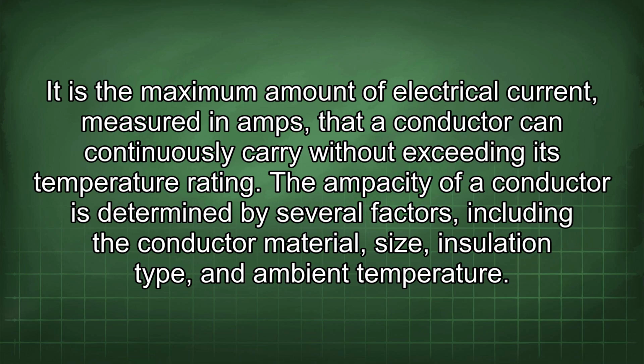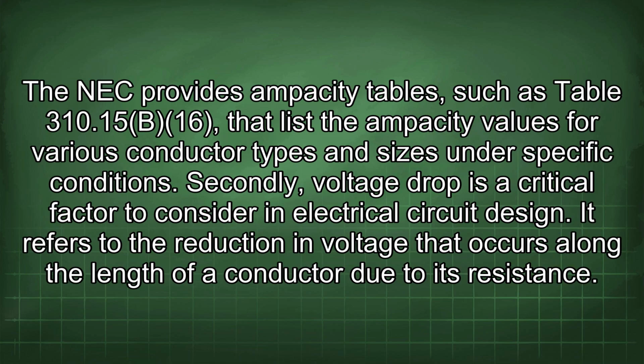ambient temperature. The NEC provides ampacity tables such as Table 310.15(B)(16) that list the ampacity values for various conductor types and sizes under specific conditions. Secondly, voltage drop is a critical factor to consider in electrical circuit design. It refers to the reduction in voltage that occurs along the length of a conductor due to its resistance.